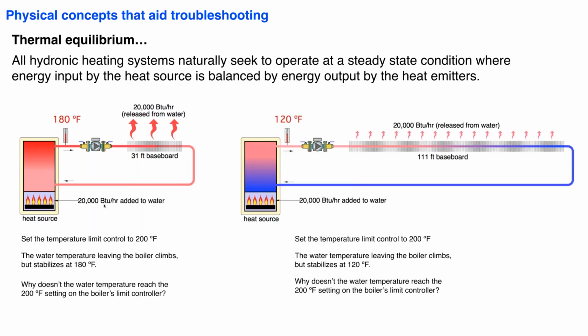Now, let's change the system. Let's go from 31 feet of baseboard to 111 feet of baseboard, all right? And let's leave the temperature setting on the upper limit control at 200 degrees Fahrenheit. So let's say the technician still thinks we can get that heat source up to 200 degrees Fahrenheit. We turn the system on. Again, we're putting 20,000 BTUs per hour into the water. With 111 feet of baseboard, we're dissipating 20,000 BTUs per hour, but our supply temperature only goes up to 120. It won't go to 125, it won't go to 130, it certainly won't go to 200.